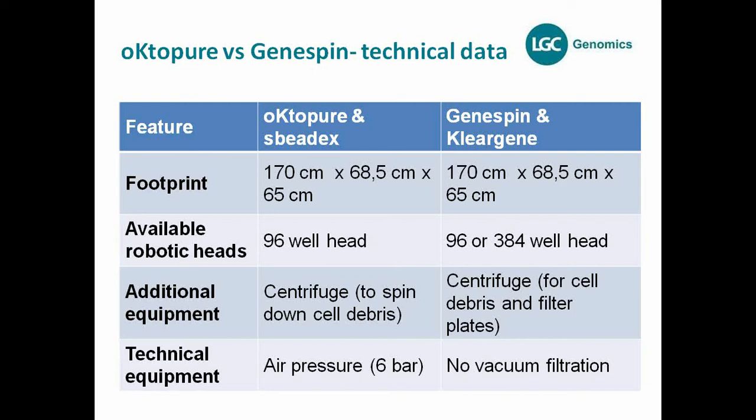Technically, oKtopure requires air pressure — 6 bar — because the head pushes tips down to their positions using air pressure. GeneSpin does not require air pressure. Unfortunately, you cannot use vacuum filtration stations for the GeneSpin robot at this time, because the Kleargene plates don't fit well in vacuum filtration, so there's no fully automated solution for the GeneSpin filter step yet.